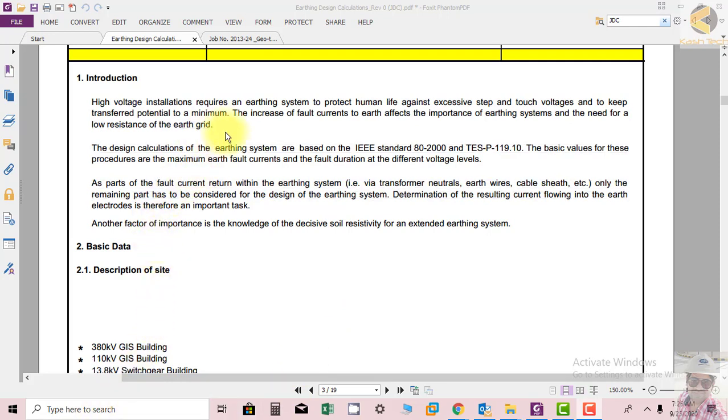That's why you will find that earthing is extremely important, and this is also one of the reasons that you will find a metallic sheath, which is grounded, in the control cable mostly. So whenever there is an insulation break, it will be shorted to the sheath, which is grounded already, and the MCB will trip in that case. So this is the same concept that we are discussing here.